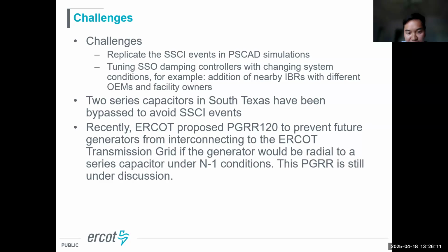Since we have seen this kind of SSR or SSCI issues in real time, we bypassed that series compensation in South Texas. We also recently tried to propose a market rule change to prevent future generation from interconnecting if it becomes radially connected to the series compensation under N-1 conditions. However, this PGRR change is still under discussion, and I'm not sure if it will pass.